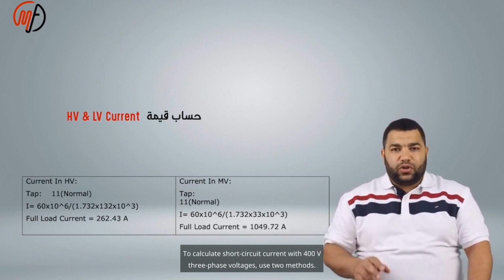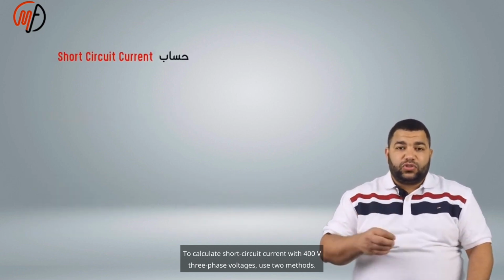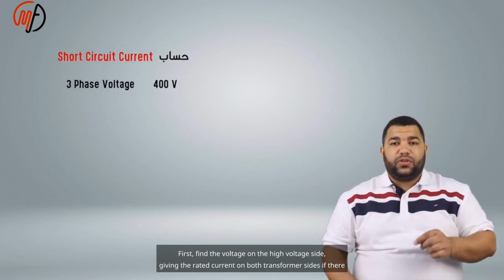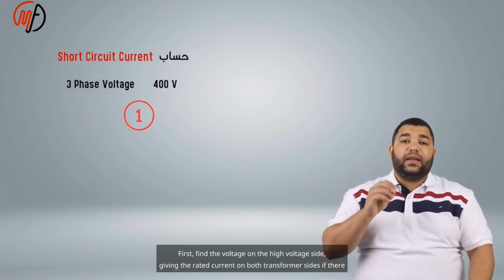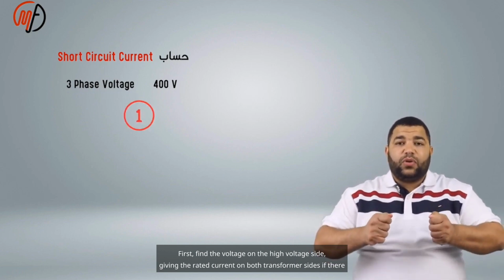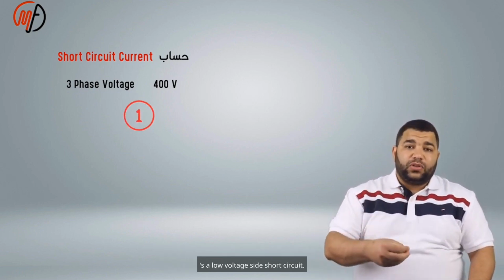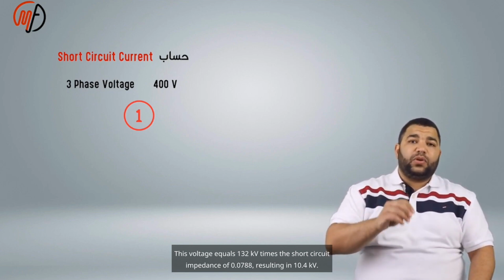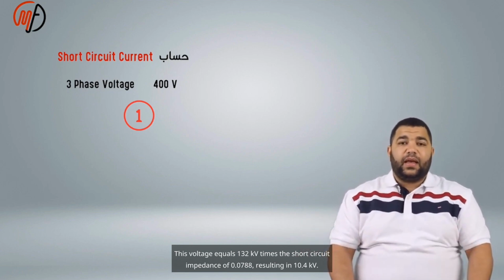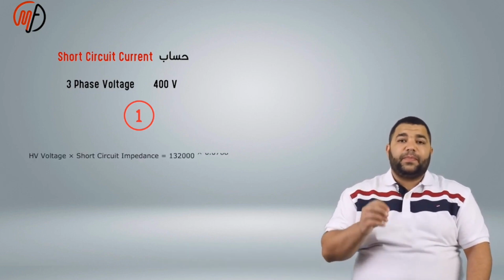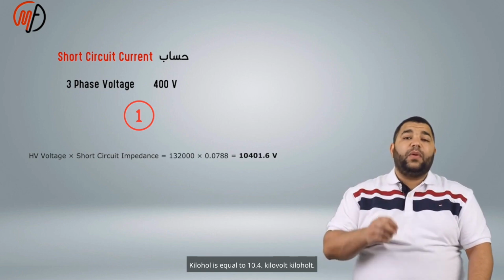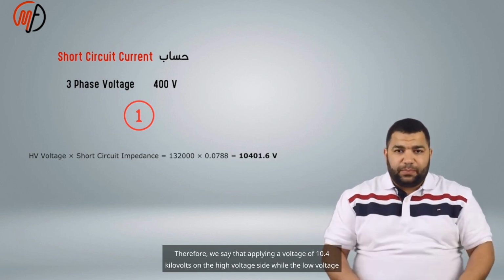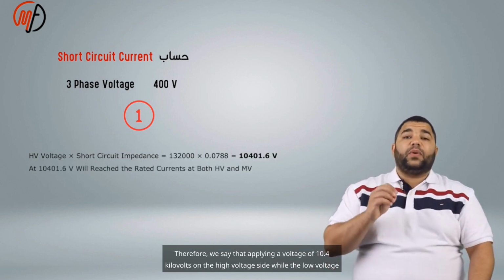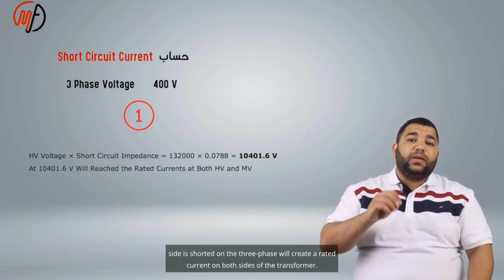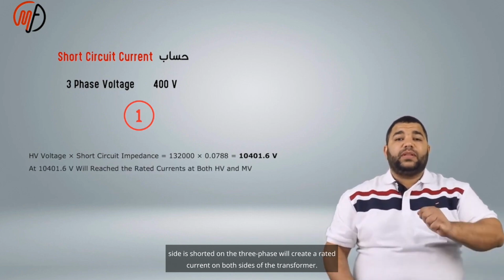To calculate short circuit current with 400 V three-phase voltages, use 2 methods. First, find the voltage on the high voltage side giving the rated current on both transformer sides if there's a low voltage side short circuit. This voltage equals 132 kV times the short circuit impedance of 0.0788, resulting in 10.4 kV. Therefore, we say that applying a voltage of 10.4 kilovolts on the high voltage side, while the low voltage side is shorted on the three-phase, will create a rated current on both sides of the transformer.